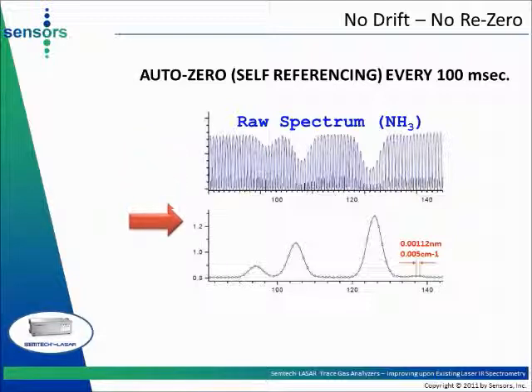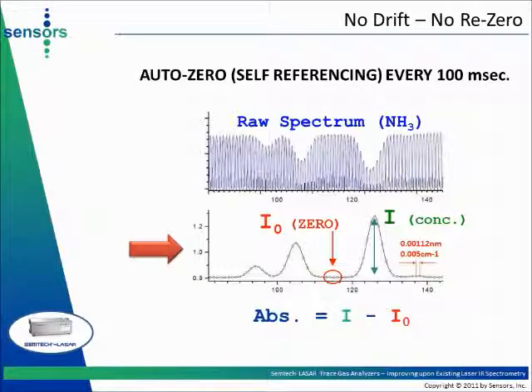The Semtech LASAR relies on direct intensity measurement at 200 wavelengths scanned every 100 milliseconds. The upper spectrum is the raw spectrum collected by the instrument — in this case, a spectrum of ammonia. The bottom spectrum is the absorbance spectrum calculated from the raw spectrum. We observe 3 clear ammonia absorption bands, as well as regions of zero absorbance. These regions of zero absorbance are used to automatically re-zero the spectrometer every 100 milliseconds. The zero information is contained in the spectrum itself, so no regular zero gas is required.